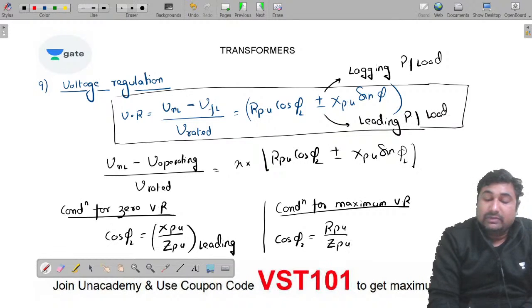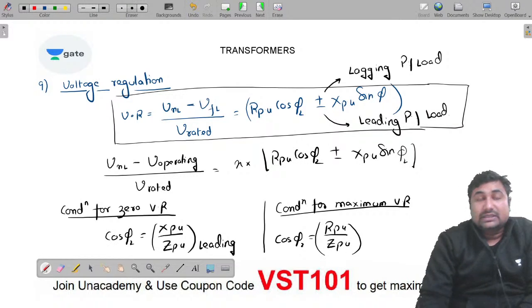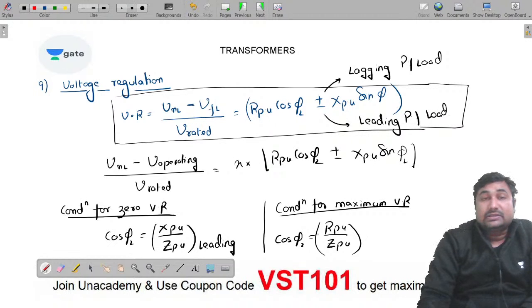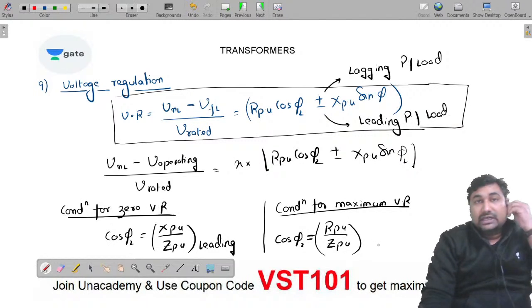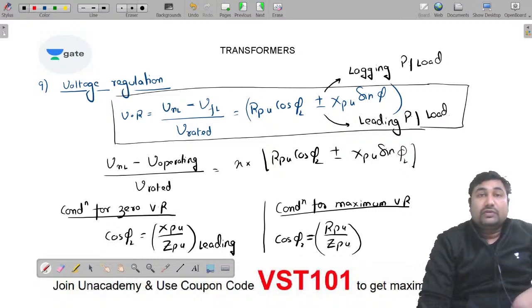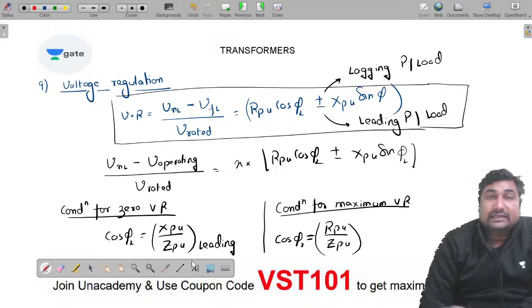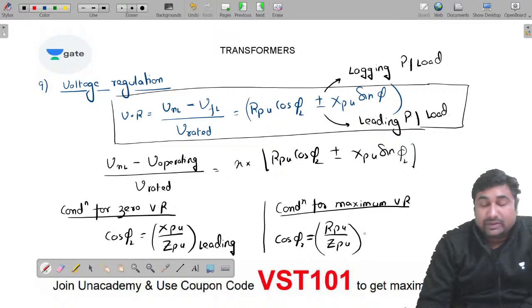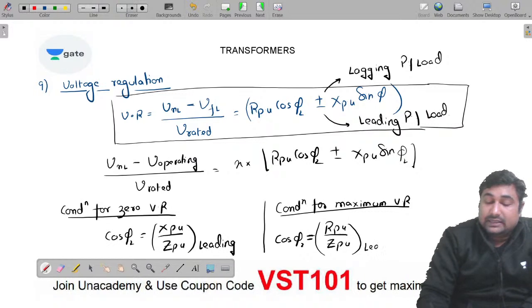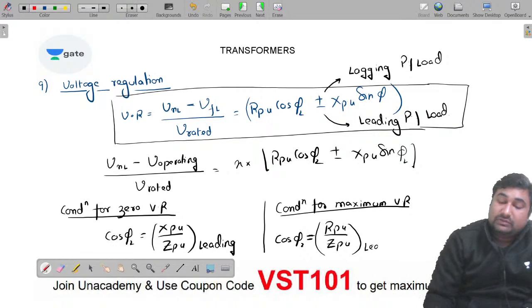How to remember this? It is very easy because R by Z is normally what we study as the power factor. So the power factor at which voltage regulation is maximum is R by Z. However, for zero it's a special case, so you write it as X by Z. It is very easy to remember. Always remember that maximum voltage regulation is only possible at lagging power factor load.